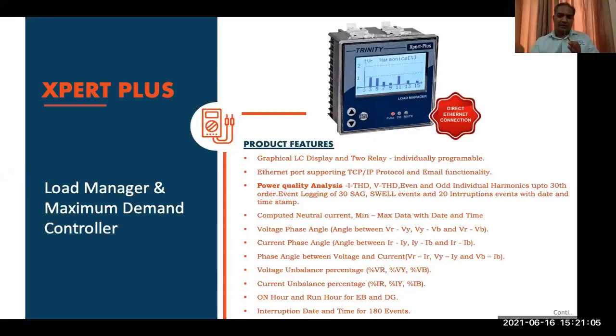Such sag events will be recorded in the meter memory. Similarly, 30 swell events. My running voltage is 240; a 10% rise in voltage is my swell voltage. So anything which goes above my running voltage, which is my allowed voltage, will be recorded as a swell event. And similarly, 20 interruption events. Complete voltage is gone for milliseconds. That interruption will be recorded with date and time.